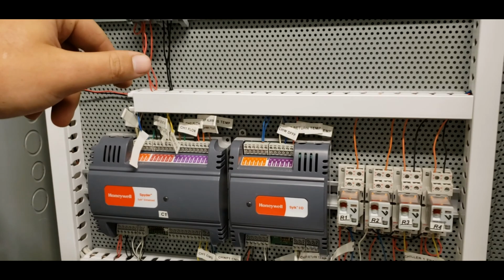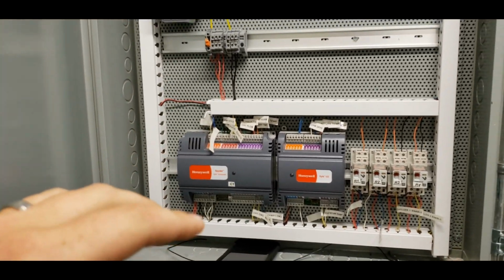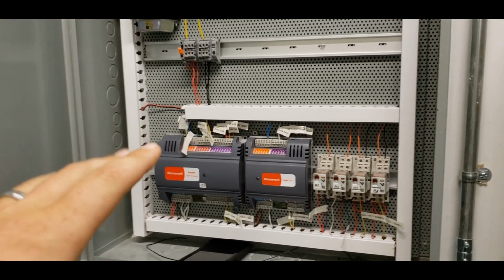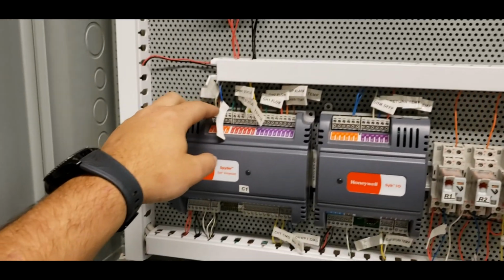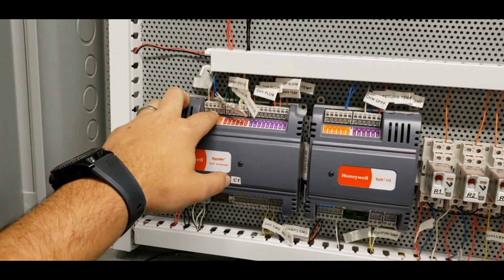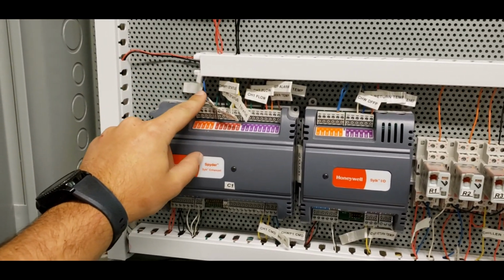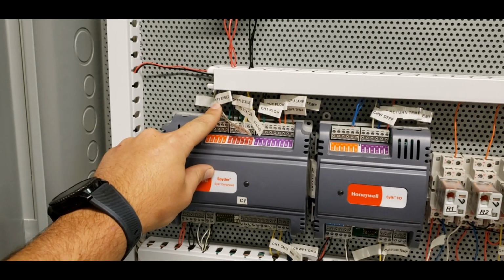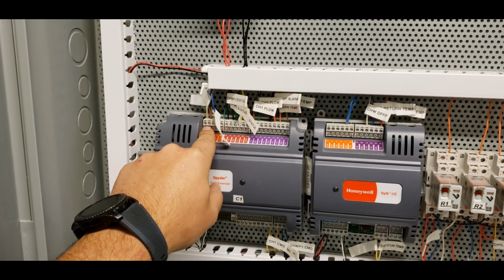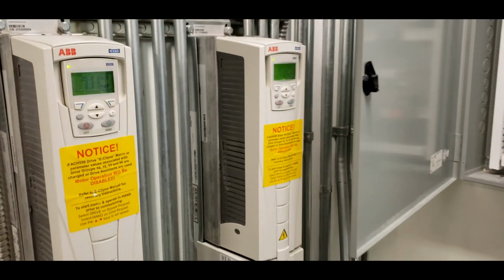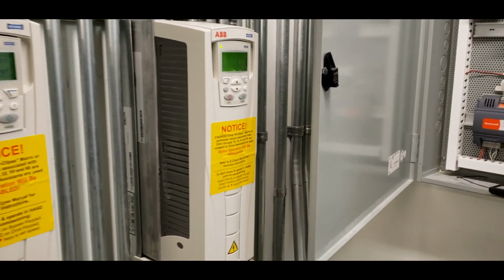I'll reestablish power, and right now it's only got chiller one to run as the primary. So what I did was the pump speed for chiller two, I tied it into chiller one's analog output, so both pumps will run and cycle together since I've got them both manually on.